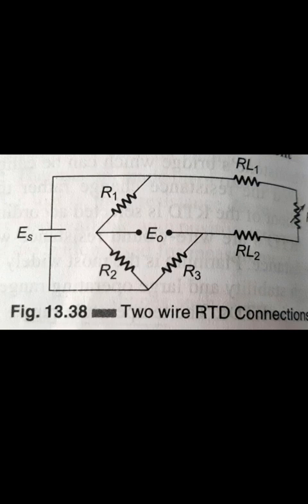compensation. The RTD commonly uses platinum, nickel or any resistance wires whose resistance varies with the temperature and has high intrinsic accuracy. Platinum is the most widely used for the RTD because it has high stability and a large operating range. The RTDs are usually connected to a Wheatstone bridge circuit.